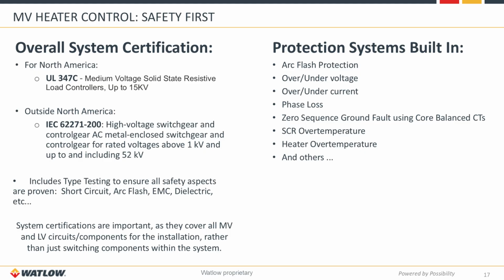These are important primarily because a systems type certification is better than just a power controller type certification. If the only thing certified in your cabinet is the actual switching device itself, the entire system hasn't been evaluated for safety with medium voltage. These two particular standards are the standards that take care of those systems certifications and are the standards that Watlow has chosen to use in order to certify their equipment.